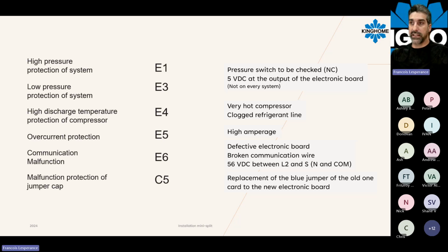E4 is a high discharge temperature protection of the compressor. Meaning we have a sensor on the discharge line here to protect the compressor if it's going to be very hot, or if you have a clogged refrigerant line, the pressure will increase and the temperature will increase. So the E4 can pop up to protect the system.